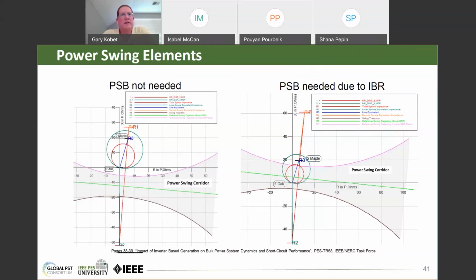On the left, I have a couple of distance elements on a transmission line, and a stability study was done, and the impedance locus passes behind the terminal. So for that particular terminal, out-of-step blocking would not be needed. On the right, at least part of that system has been changed, where conventional synchronous generation has been changed to inverter-based resources. This is just an example, and you can see that the impedance locus now passes through the line, through zone 1 and zone 2. And so power swing blocking may very well be needed. It looks like it will be needed, at least in this case, due to the swing rates being changed. And this has to do with changes in inertia of the system.